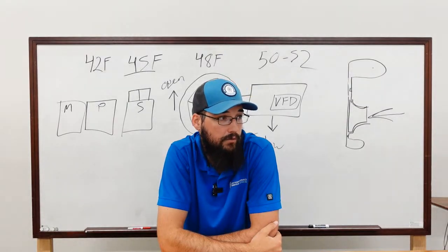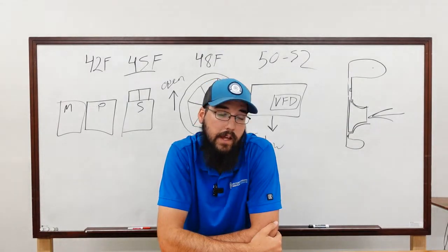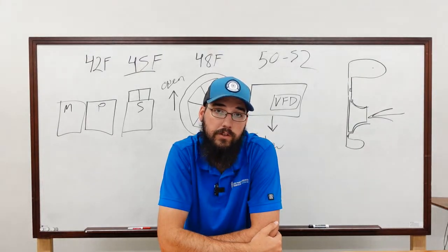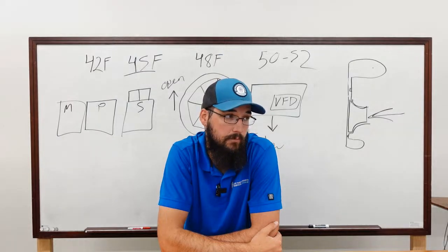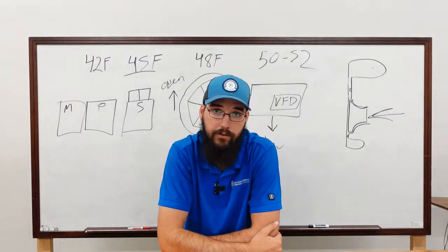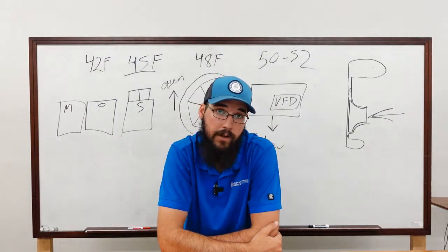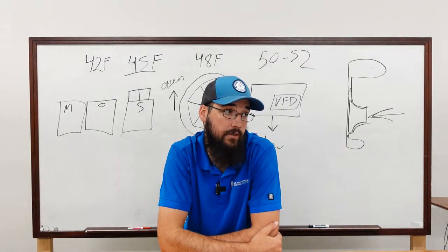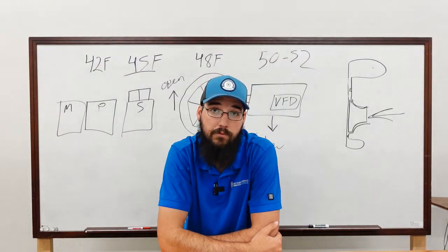Now, say you have a system where you're in a pinch, okay? We have this bank of chillers, and we have two cooling towers that serve it. One of those cooling towers went down. It lost its fan, whatever, you name it. We don't have a cooling tower now. We needed both of those towers to maintain this system. The service call came in because our chillers were surging.